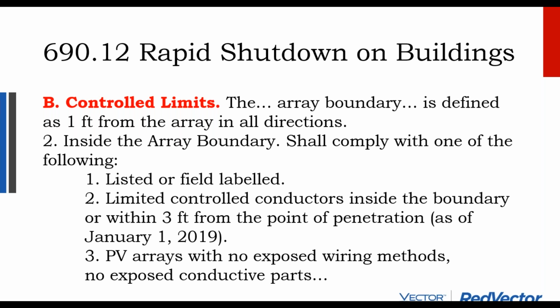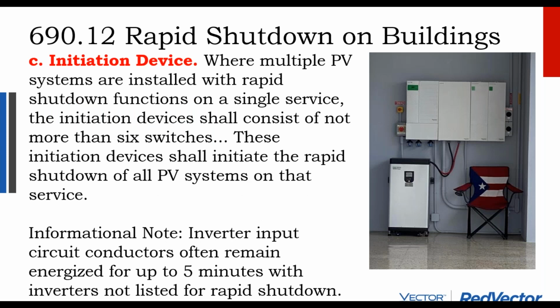So I don't know if that solar shingle exception is going to remain in code very long. Maybe it will, maybe it won't, but by and large, most solar arrays aren't solar shingles, and most solar arrays need to have these module level control boxes, at least in the United States. It's not part of international building code, it's part of national electric code. And so we see in this picture here, there's a little rapid shutdown initiation button that the fire department can show up, press this button and initiate rapid shutdown to disable the array up on the rooftop.